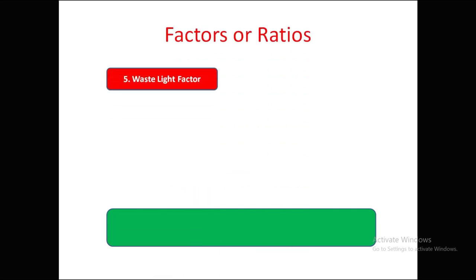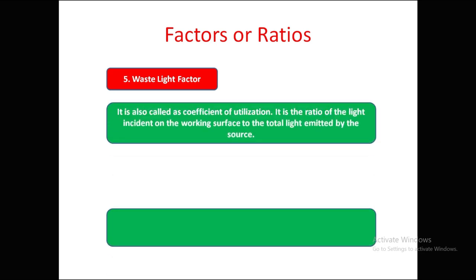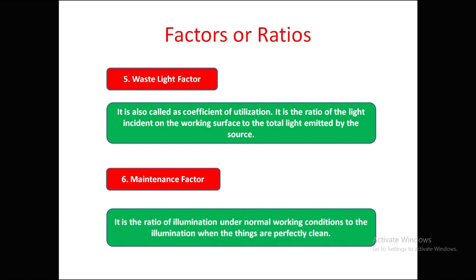Waste light factor is also called coefficient of utilization. It is the ratio of light incident on the working surface to the total light emitted by the source. Maintenance factor is the ratio of illumination under normal working conditions to the illumination when things are perfectly clean.